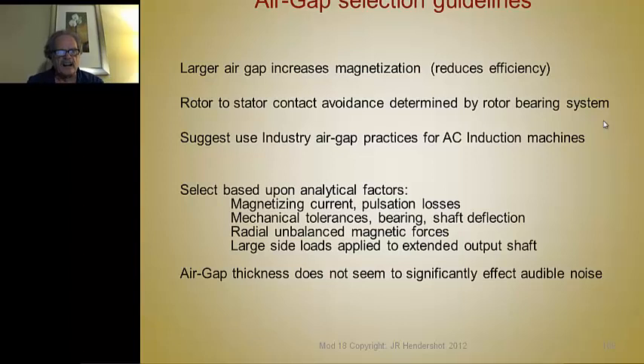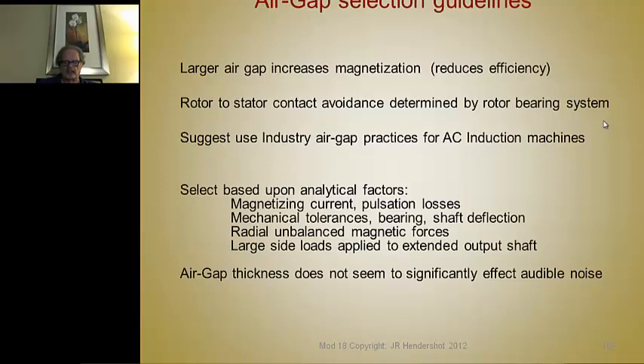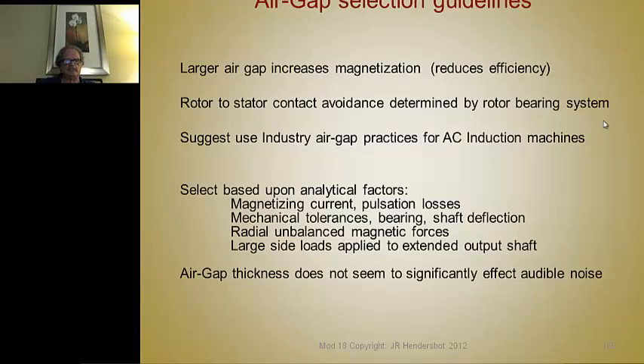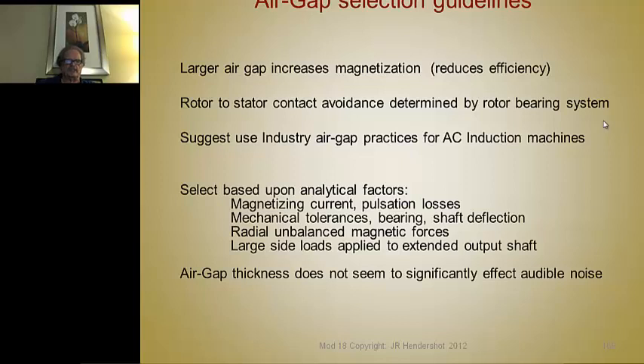With respect to the air gap: a larger air gap increases the required magnetizing current, which reduces efficiency and power factor. But if the gap is too small, you can have rotor-to-stator contact, which must be avoided at all costs. That's determined by the rotor bearing system — whether the bearings are preloaded and mounted with the right fits. Standard practice is that the inner race of the bearing should be an interference fit on the shaft, while the outer race mounted in the stator needs preload.